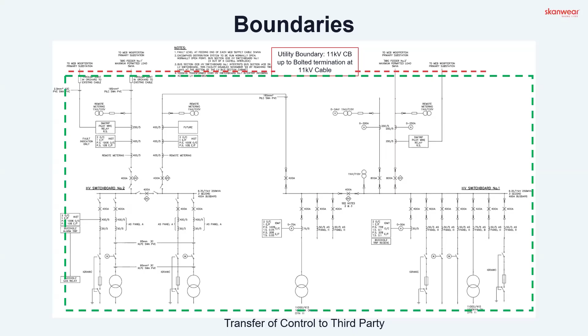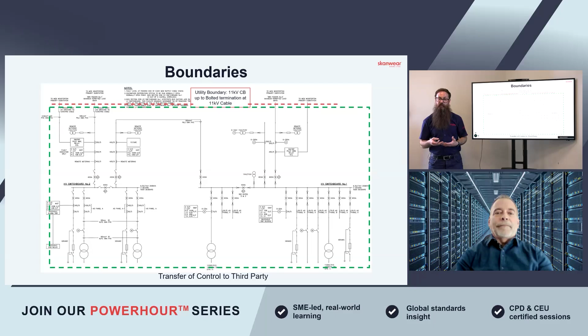So those boundaries need to be known. I've had some examples in the last 6 months where a network's been transferred over and some of the guys were continuing to work on the downstream HV or MV apparatus because they just continued business as usual. It didn't impact the work, but in reality, it's not under their control anymore. So everybody in those communications on a transfer of control process, anyone that's impacted by that, needs to be made aware, because once it's transferred across, that's all under the operational control of the third party. It's no longer theirs to operate. So again, those measures need to be put in place. It's something to be aware of.